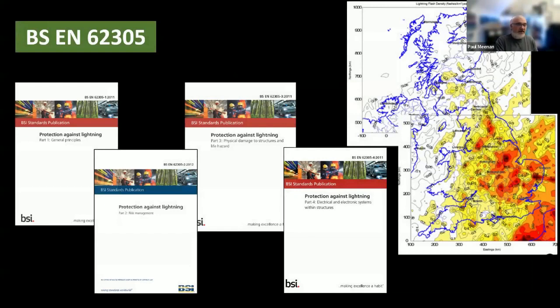Now in England, just coming back on the HV side, we have something called atmospheric transients, lightning protection, and we have four BS EN standards, 62305. Part 1 is your general fundamental principles, part 2 your risk management, part 3 the physical damage to structures and life hazards, and part 4 the electrical and electronic systems within the structures. Now in England, we do a risk assessment. We use the guidance, as you can see on the screen, we use flash density maps, where the weather services record all the lightning strikes so that we can ascertain the level of risk so that we can design a proportionate lightning protection system. So lightning protection systems are risk-based. So if you have a risk assessment, then you will design from the risk assessment.